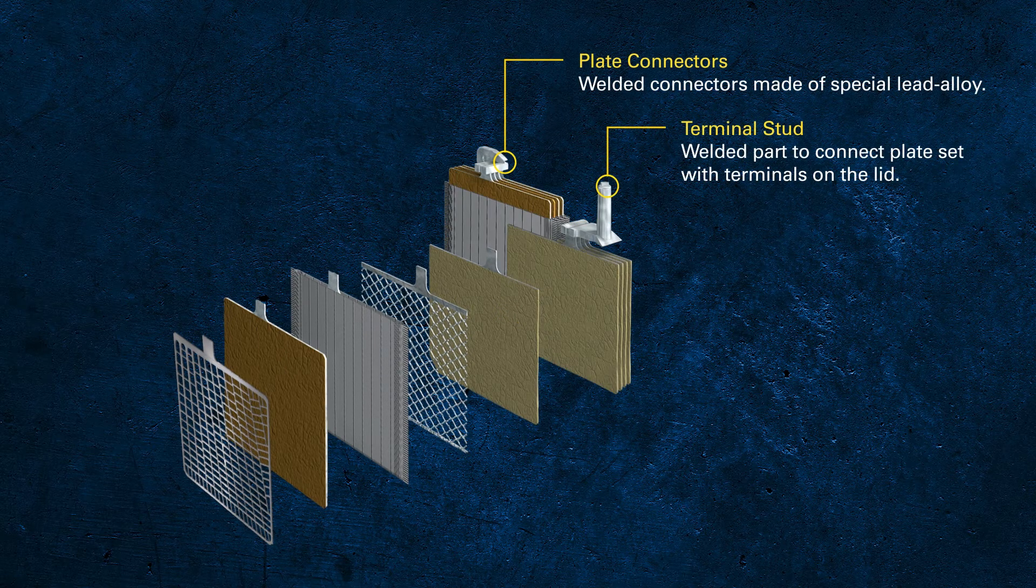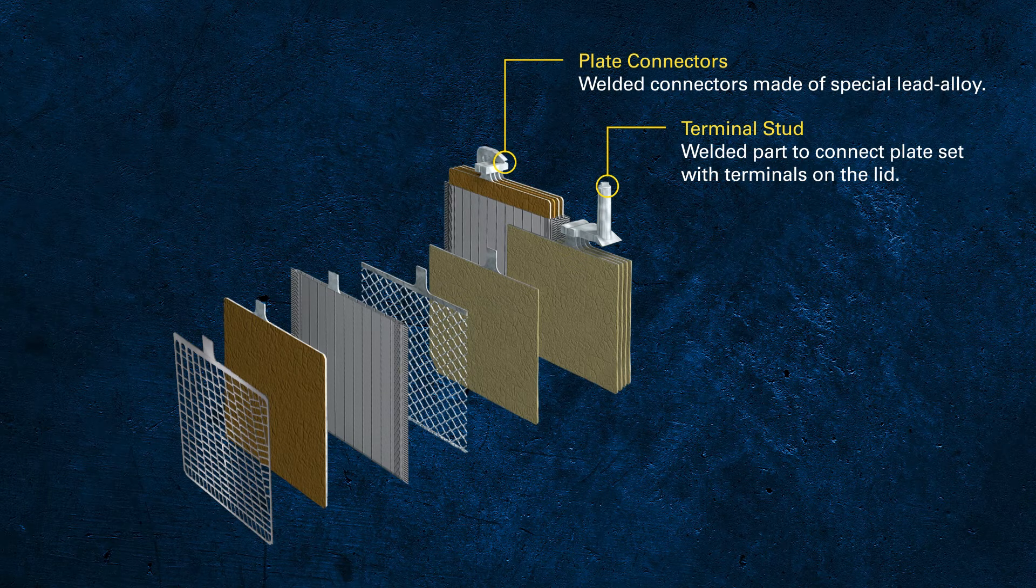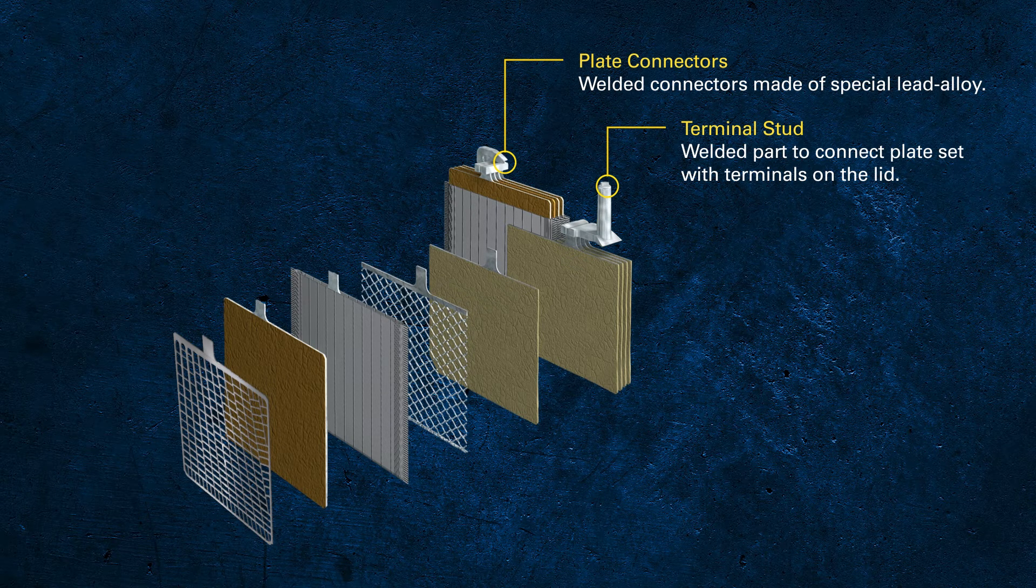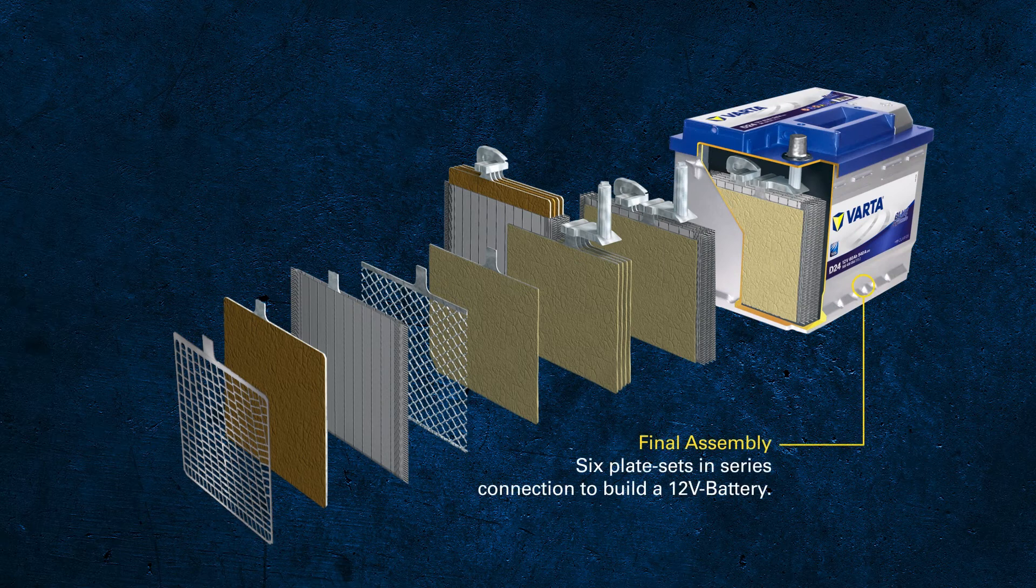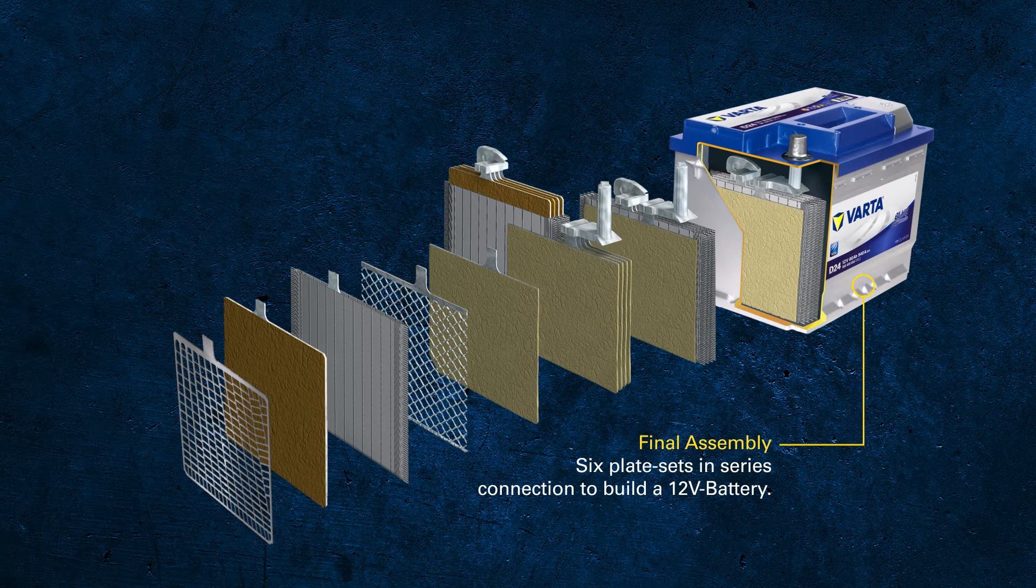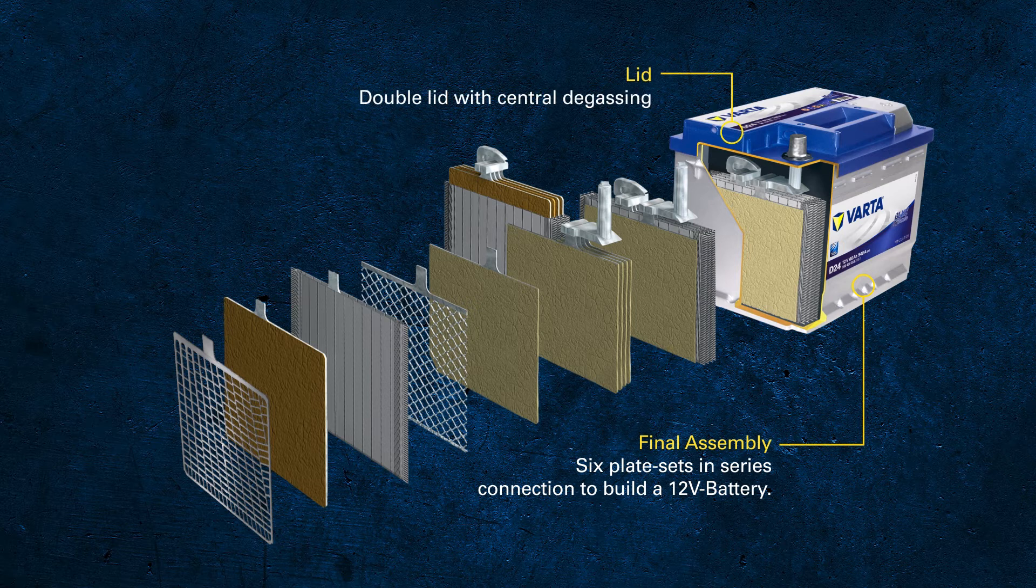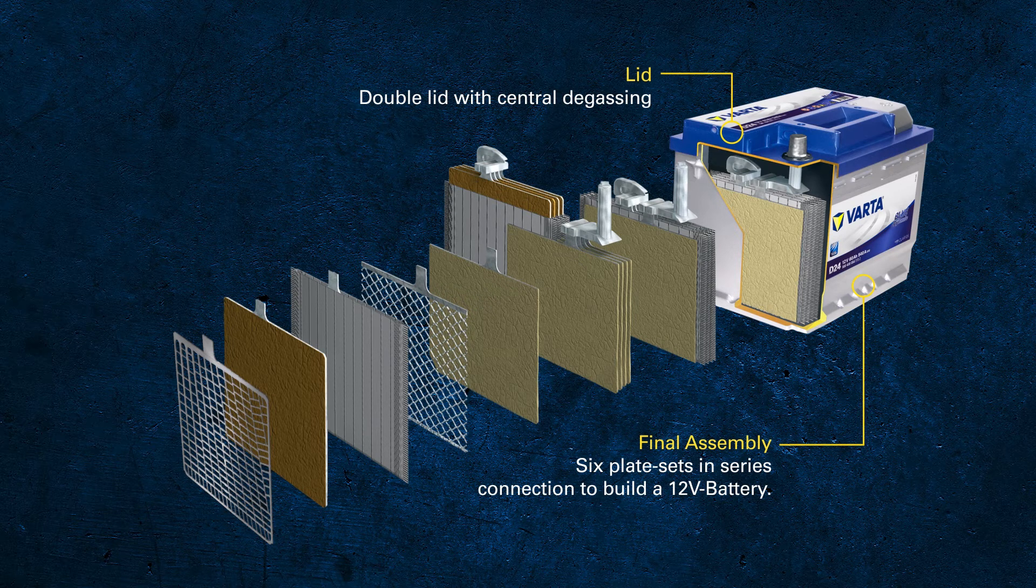The positive and negative plates are connected in parallel by a welded connector that is either connected to the battery terminal or to the next cell. In total, a 12-volt battery is made of six cells connected in series, each containing positive and negative plate sets. On top of the container there is a special lid that provides a central degassing outlet and a special flame arrester to avoid sparks from outside igniting the gases inside the battery.